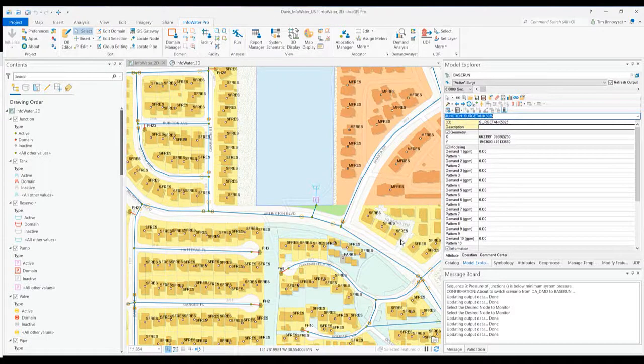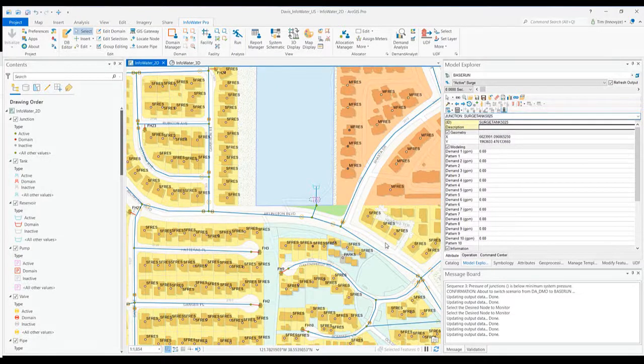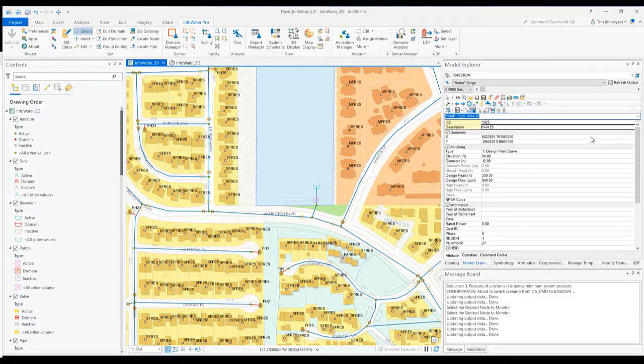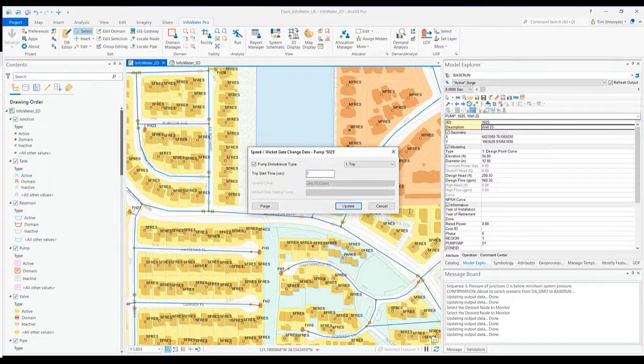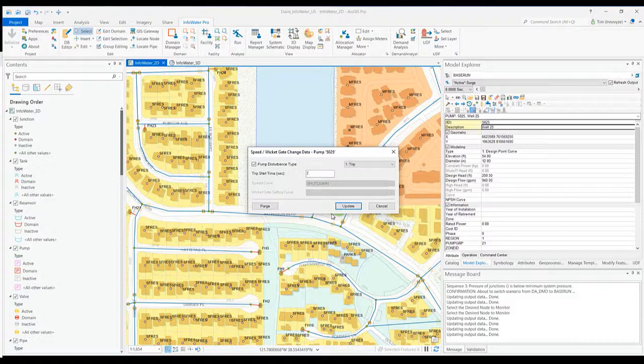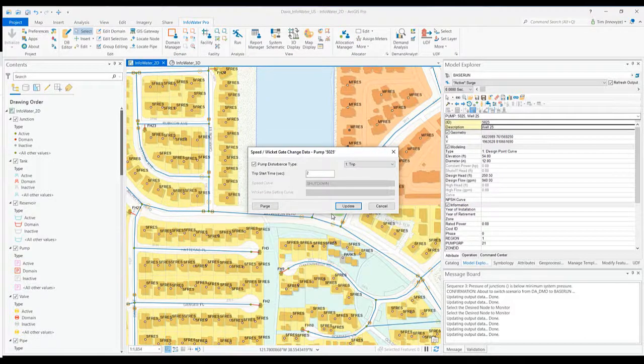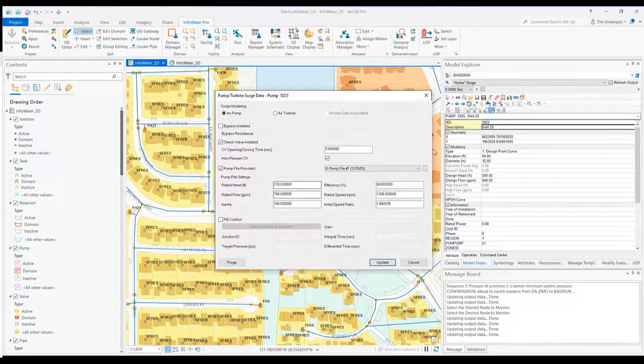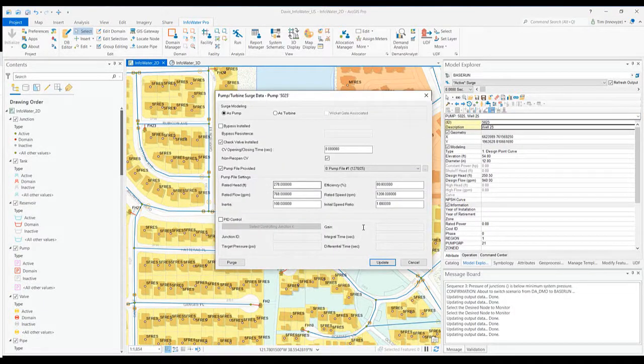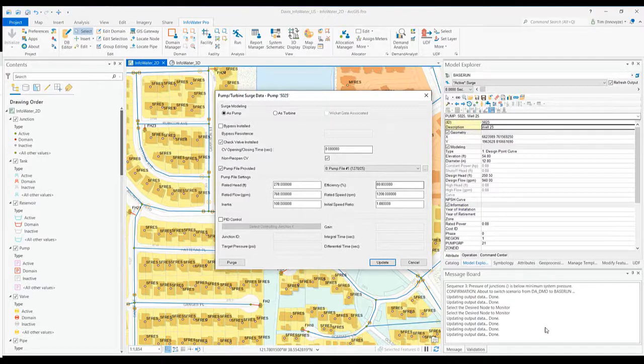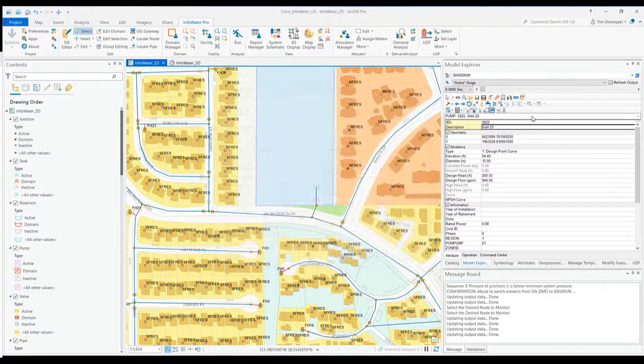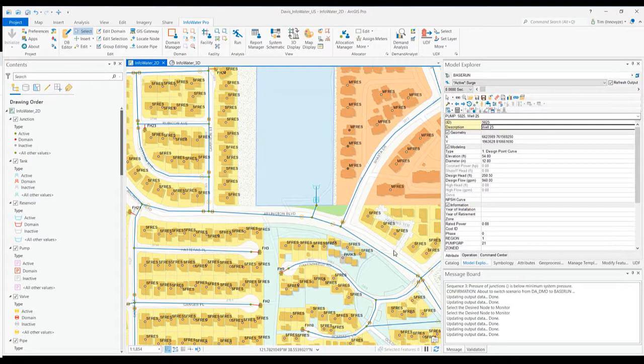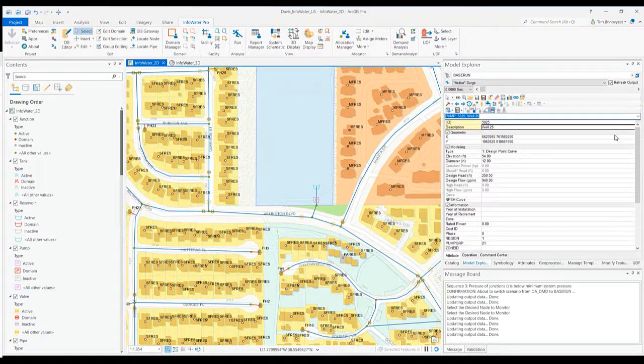If we look at our pump and the different settings for how it's shutting off, when it's tripping you can specify it takes two seconds to actually go from pumping to having that trip event. There are other parameters you can specify: what should the head be, what was the flow before it tripped, how long does it take for that check valve to go in. Here I've made it very small, actually nothing, to really make this a large transient event, make it viewable for you.